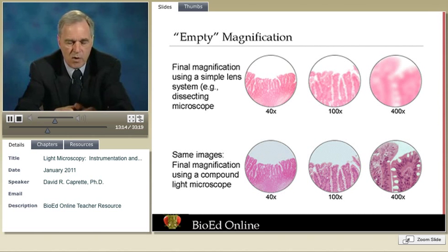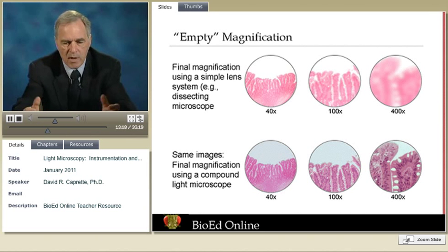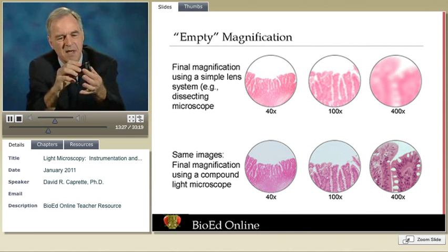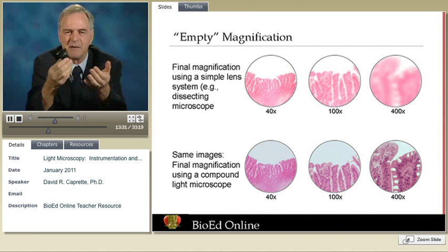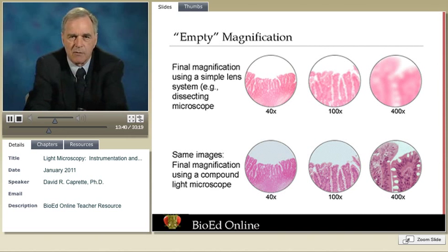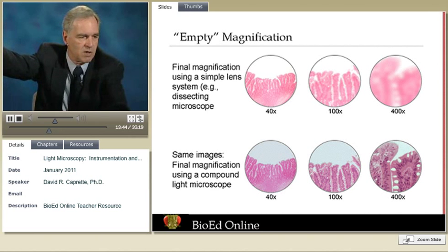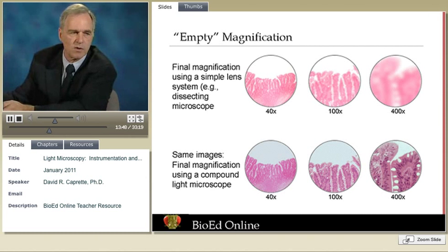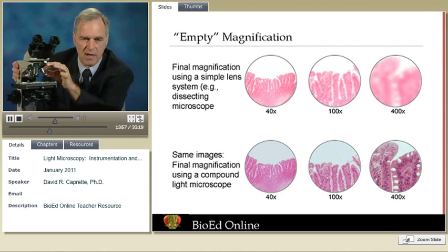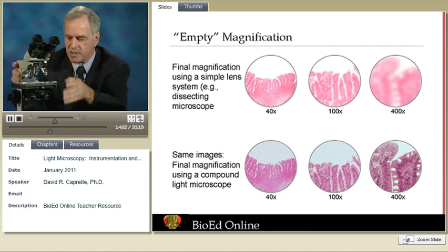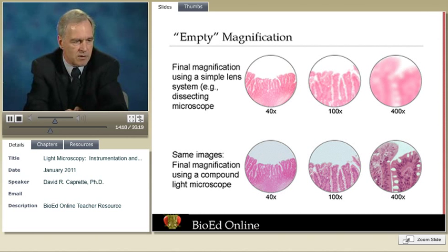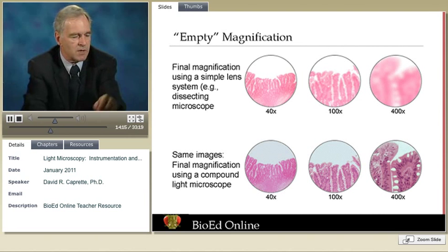At 40 power — about the limit of a dissecting microscope — we can get a pretty good image with a lot of apparent detail. We could go up to 100 power by using a 25-power eyepiece instead of a 10-power eyepiece, but we wouldn't gain anything — we wouldn't see any more detail, just magnify a blur. At 400 power with empty magnification, it isn't even worth looking. With proper objective lenses in combination with eyepieces, we get very good resolution — magnifying a high-resolution image so that even at 1,000 power we see excellent detail and good contrast.